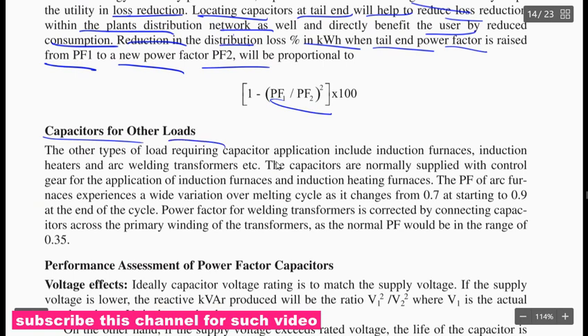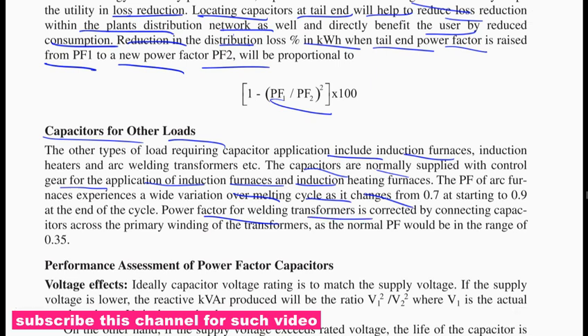Capacitor for other loads. The other types of load requiring capacitor application include induction furnace, induction heater, arc welding transformer. The capacitors are normally supplied along with the control gear for application in induction furnaces and induction furnaces. The power factor of arc furnace experiences a wide variation. In one melting cycle it changes from 0.7 at the start to 0.9 at the end of the cycle. Power factor for a welding transformer is corrected by connecting capacitance across the primary of the welding transformer. The normal power factor should be in the range of 0.35.